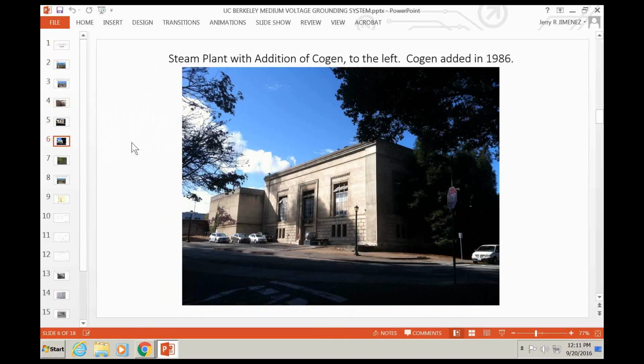Around 1986, cogeneration was a hot topic, I know certainly in California and I believe all around the country, and the university decided to get into that. So they built an addition to the steam plant right over here on the left-hand side. That's called the cogen plant. So most of the cogen plant is in there. There's a big gas turbine about 25 megawatts and a smaller steam turbine about 5 megawatts. And of course there are lots of interconnections with steam and wiring between the old steam plant and the cogen plant. So where's your exhaust heat coming from?